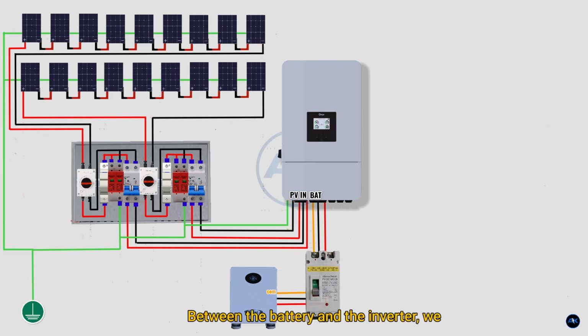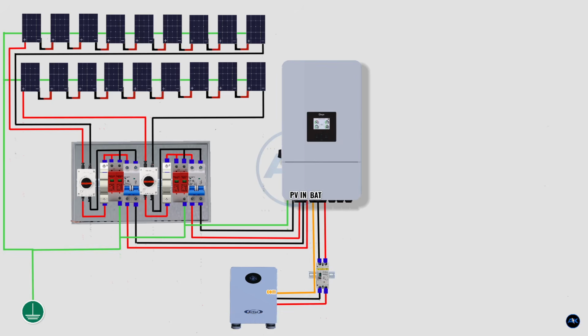Between the battery and the inverter, we install a 250-amp DC breaker. This breaker provides essential overcurrent protection and allows you to isolate the battery during service or emergency shutdowns. Once the breaker is installed and the cables are secured, go ahead and bond the battery cabinet to the system's grounding network. With the wiring complete, we can now power on the battery and verify communication with the hybrid inverter.